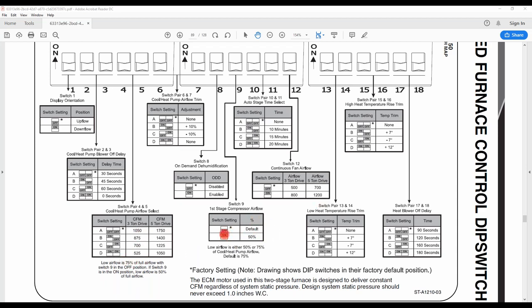A lot of people ask, well, what's the difference between the 75 and the 50%? When would you use a 50% airflow? So flipping dip switch number 9 to the on position, you're only going to get 500 CFM instead of 1,050. The 50% airflow is when you're using a tandem compressor on a 2-stage outdoor unit. Typically, those compressors are split evenly 50-50 and not 75-25.